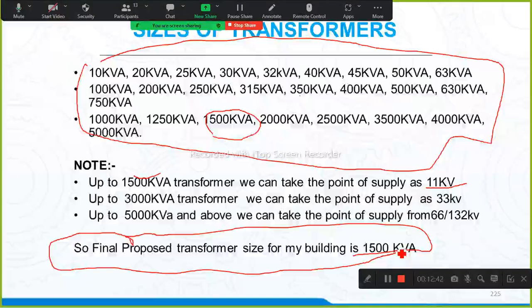Adding up the total load, taking 10% extra for future expansion purposes, calculating the maximum demand based upon the demand factor of the building. 4th is calculating the kVA required based on the power factor, and 5th is calculating the maximum kVA required based upon the derating factor of the transformer. Considering all this, we got the transformer size as 1500 kVA.